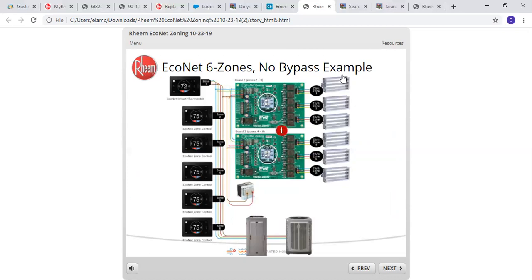So here we go, Econet 6 zones, no bypass example. We've got our dampers 1 through 6. We're at the end of our chain. We have our outdoor unit, so we're going to go 4 wires in, RC, E1, E2, into the furnace board, daisy chain out of the furnace board.